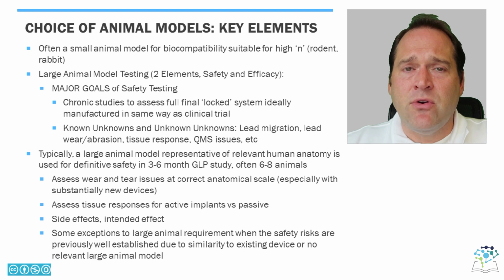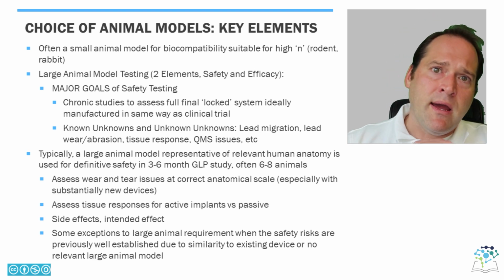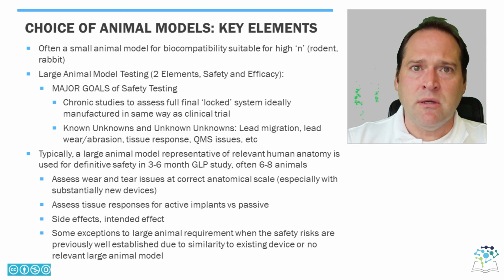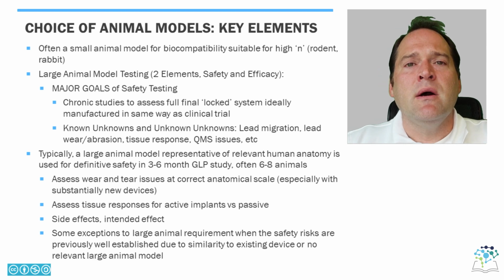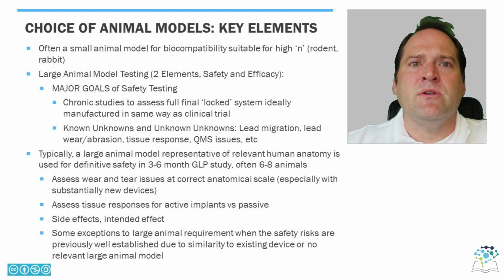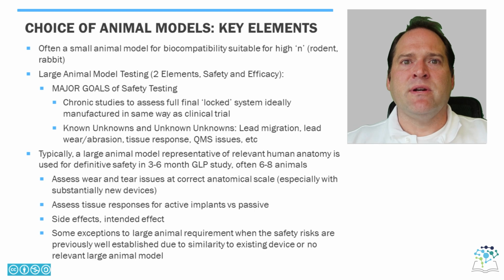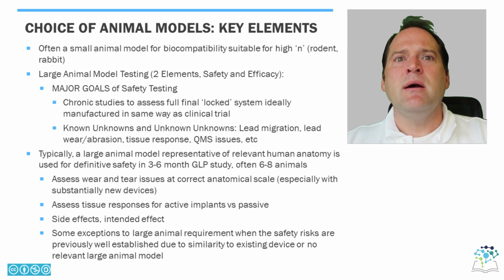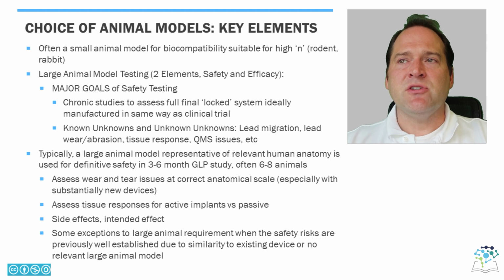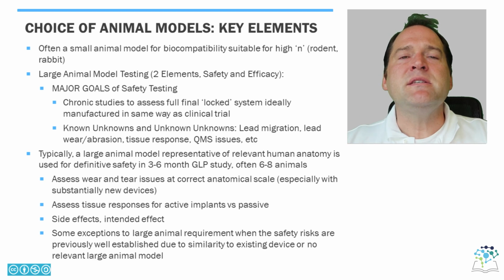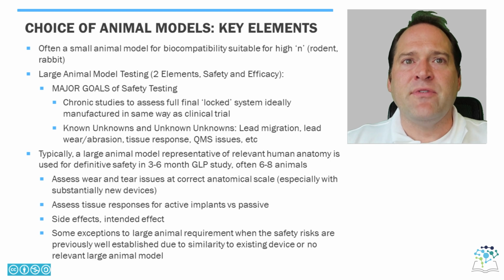For implantable electrodes, whether it's on an artery or a nerve, as you move around, especially a large animal, you put a lot of torque on them. You see a lot of failure at transition points between a pulse generator and silicone leads, or when the silicone leads actually change in terms of their size and lumen diameter, and that you have filler and things like that. Those are things that tend to fail chronically. This allows the FDA to see this at scale.